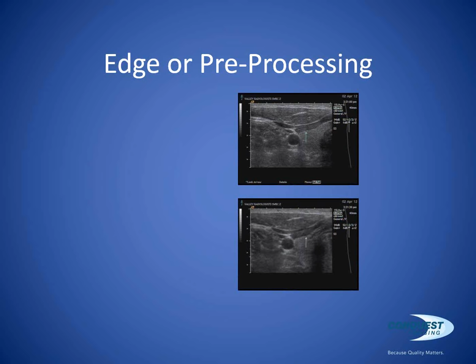And you're actually looking at that on these images here. Edge or pre-processing is a sharpness control for an ultrasound machine. That's what it means. What it does is sharpen the edges or borders of structures. In the very top image, I'm using the highest edge or pre-processing possible, a +3. In the bottom one, I'm using a -3. The proper setting is usually somewhere in between.